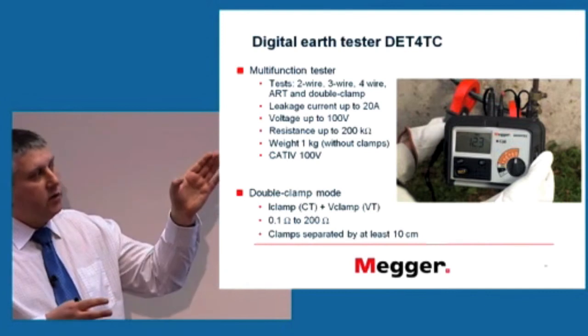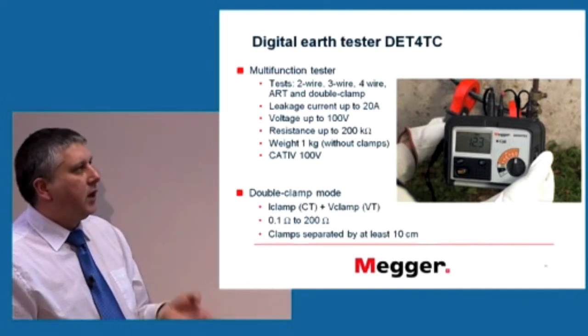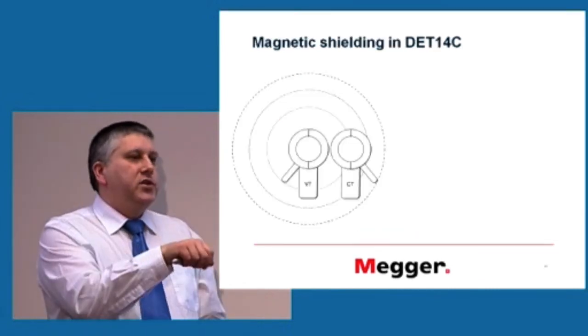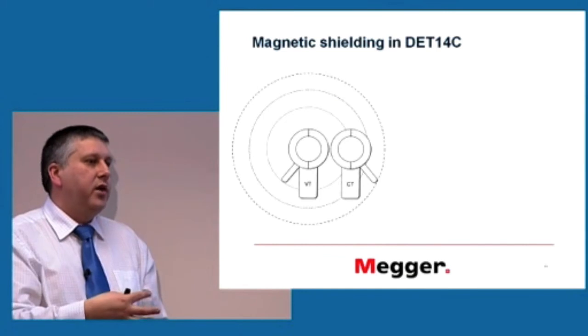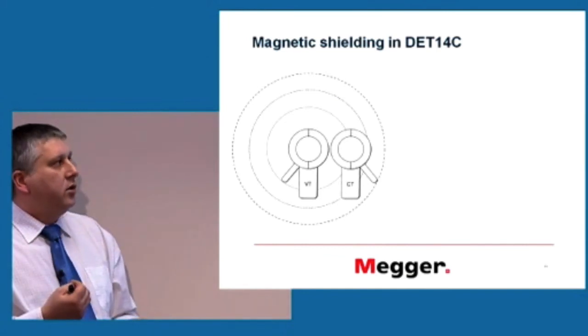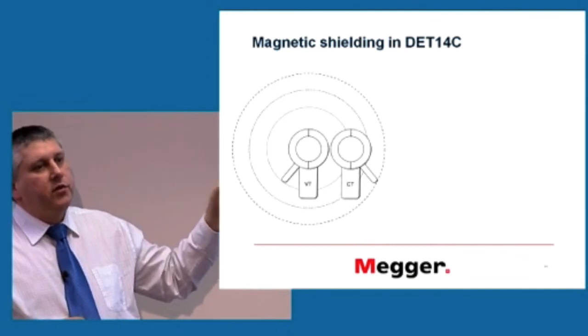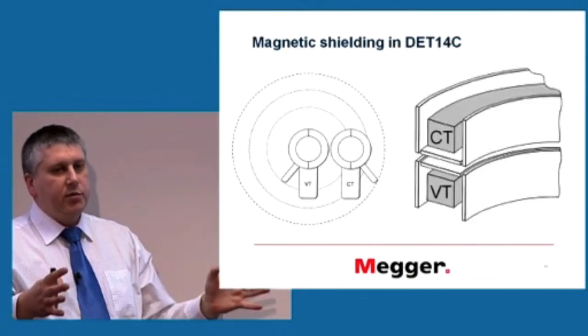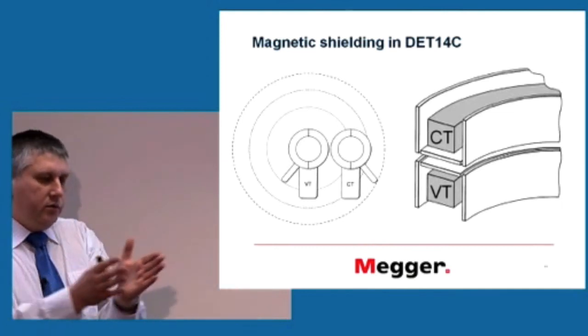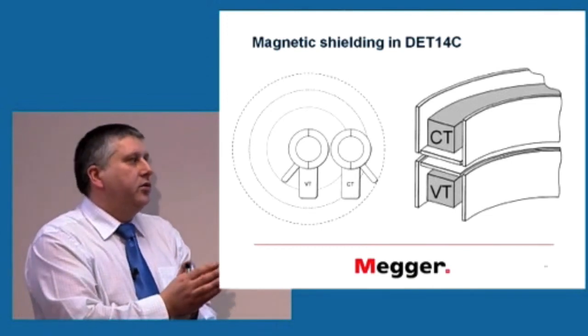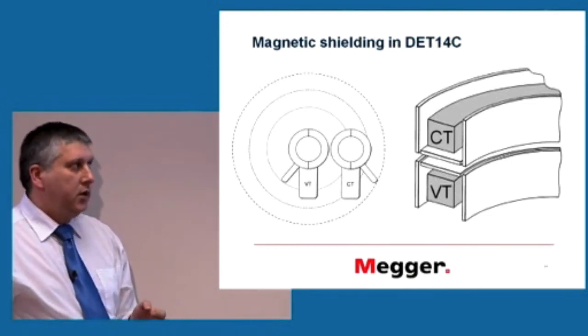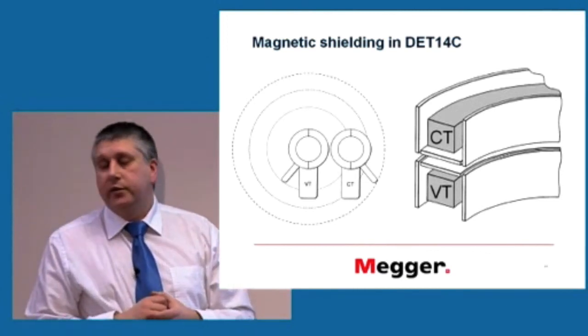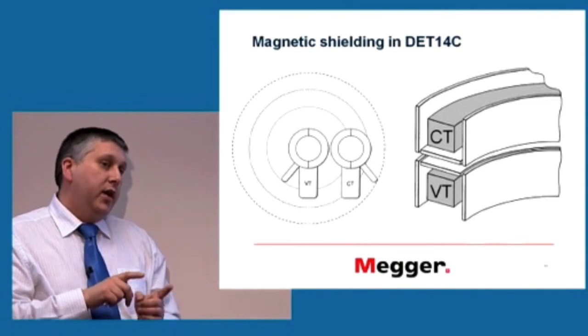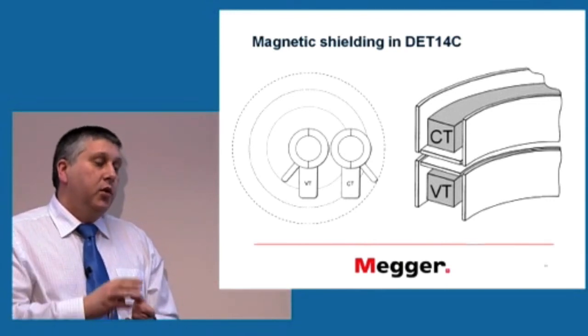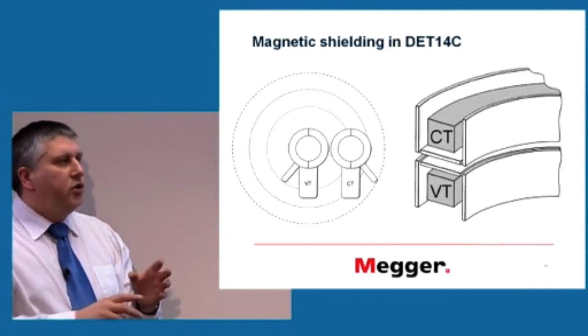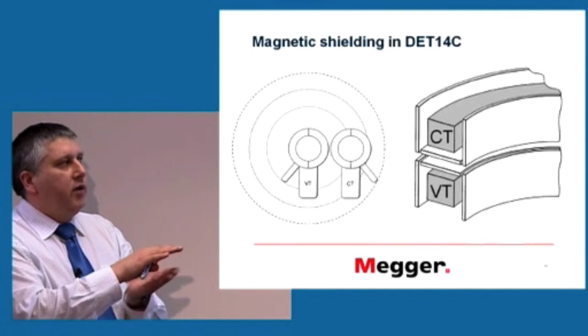However, the clamps, as you can see even in this image, have to be separated by a certain distance. This is because our voltage transformer is excited and it generates a magnetic field around it. Because the currents induced are so small, that electromagnetic field around the voltage transformer can affect the current transformer. So you have to keep them in physical separation. If you want to bring them closer, there's really only one thing to do, which is to introduce shielding. And this was part of the project we did with Wolfson Centre, where we looked at how close we can bring those two, and whether the shielding will stop that harmful effect, not related to the loop we want to measure, but the direct interaction between the voltage transformer and the current transformer.